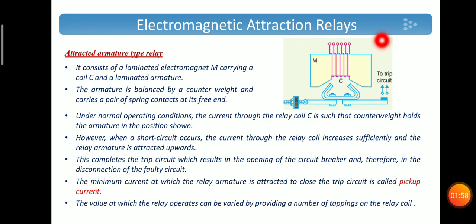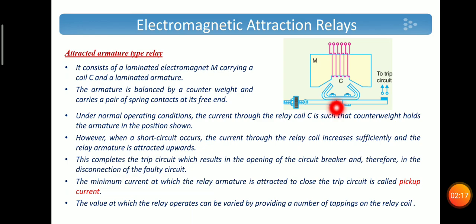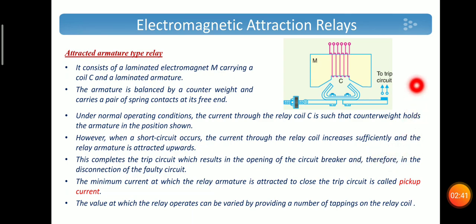This coil is connected to the line or apparatus to be protected and it carries the current in the transmission line. When a fault occurs, the current in the line increases, producing more attractive force than the counter weight, and the armature is attracted by the electromagnet. When the armature is attracted upwards, the trip circuit gets closed due to the spring arrangement, resulting in opening of the circuit breaker and disconnection of the faulty circuit. The minimum current at which the relay armature is attracted to close the trip circuit is called the pickup value of current.